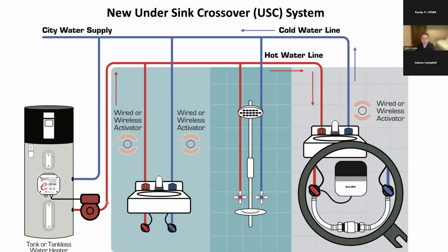Now the pump is pulling hot water from your tank and moving it through your pipes very fast. All the cold water that has been sitting in your hot water line is going to get pumped in through this bypass and into your cold water line. So this little cross connection allows circulation to occur in your plumbing, and now you have hot water that's moving. Now, when this temperature sensor sees a 6-degree rise in temperature, only 6, so if it's going from like 60 degrees to 66 degrees, that rise in temperature indicates that 115, 120 degree water from your tank is just a few seconds away. So then this sends a wireless signal back to the pump to turn off.